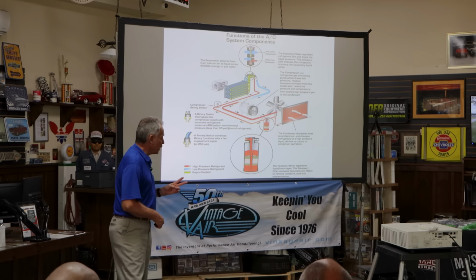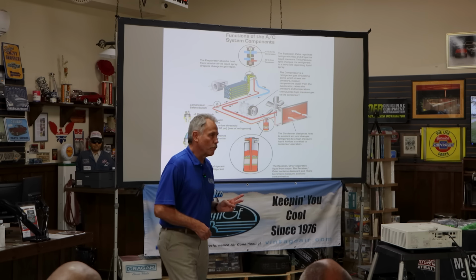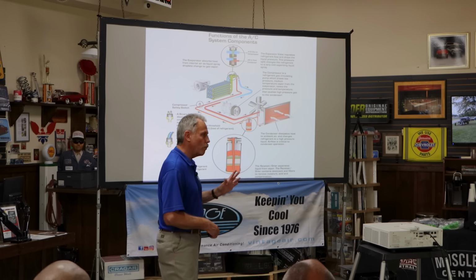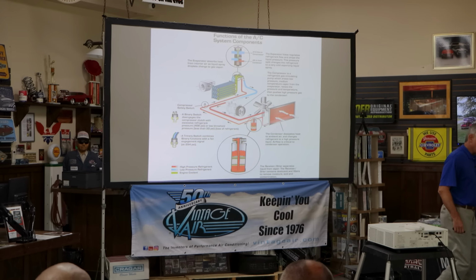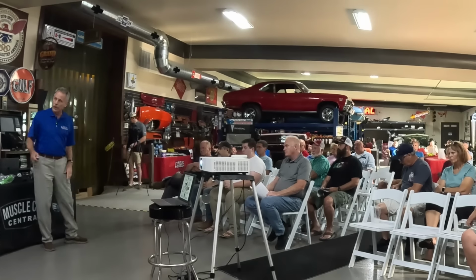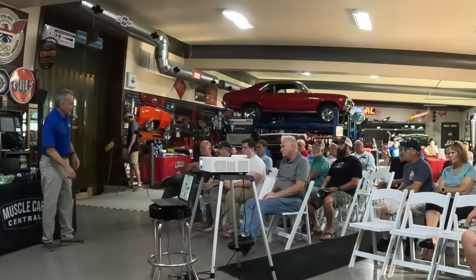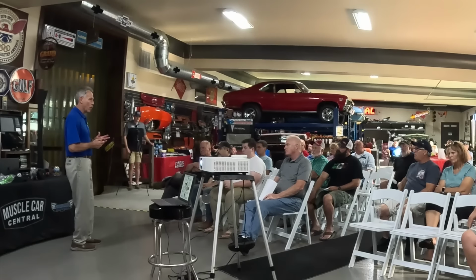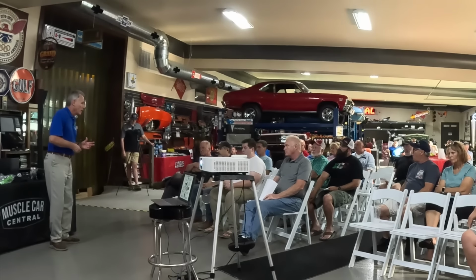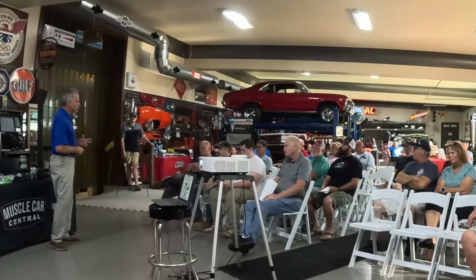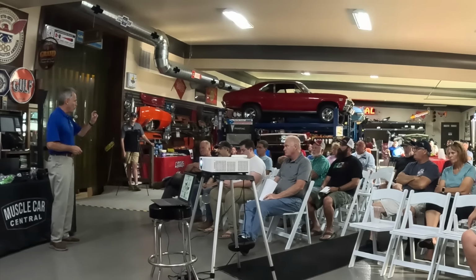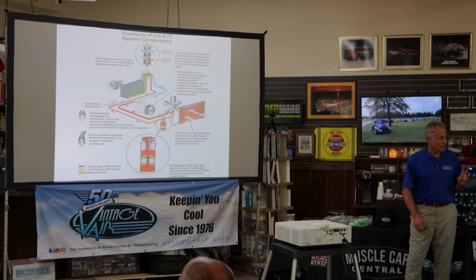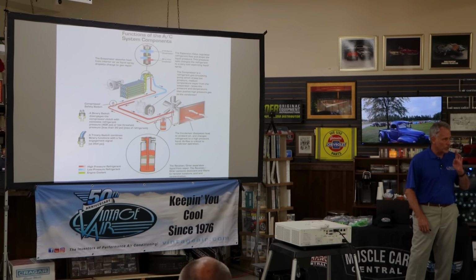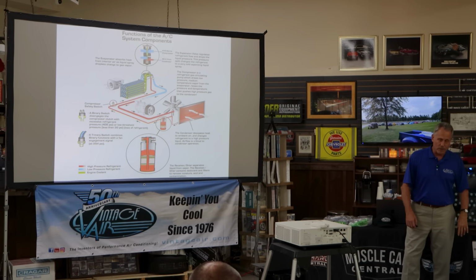The second function is it removes any moisture from the refrigerant. You don't want any water or moisture in your refrigerant - you want it to be pure. If there are minute amounts of water in the refrigerant, the desiccant in the receiver dryer will absorb that water. That desiccant is very similar to the little white packets you find in electronic products like a stereo - that's a desiccant, and it's there to absorb moisture. So that's your second function: absorbing any moisture in the refrigerant, because you don't want any moisture in there.